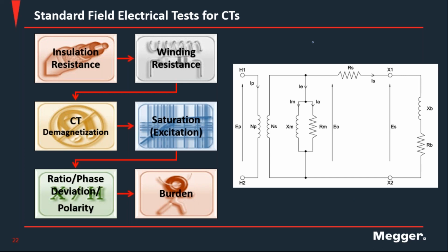The only thing, remembering what I talked about in my previous question, is that you want to run a demagnetization in between or after those DC measurements, just to make sure that probable remnant flux in the core does not affect the subsequent test. So if you select your sequence manually, no issues, just make sure you run a DMAG after any DC measurement.